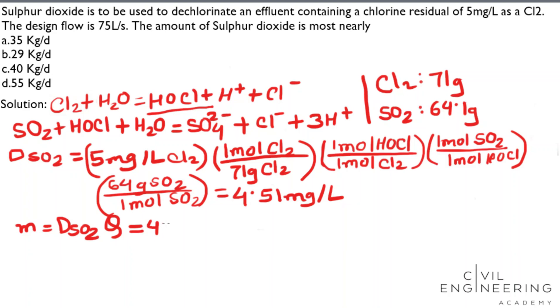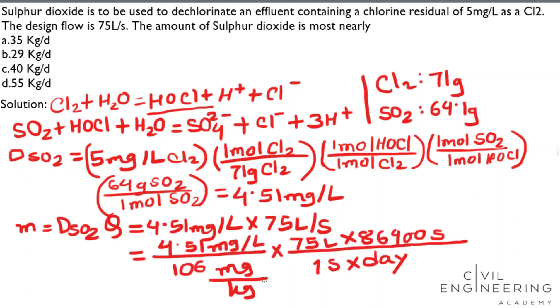Here, 4.51 milligram per liter multiplied by our design flow 75 liter per second. I convert milligram into kilogram and seconds into day. After calculation, I get the value 29.22 kilogram per day.